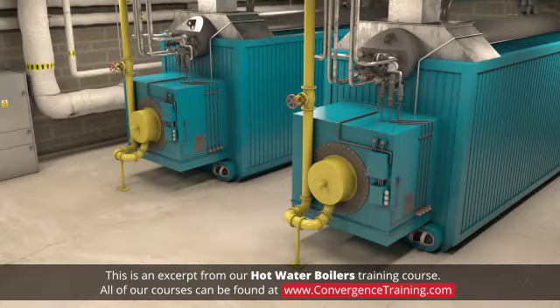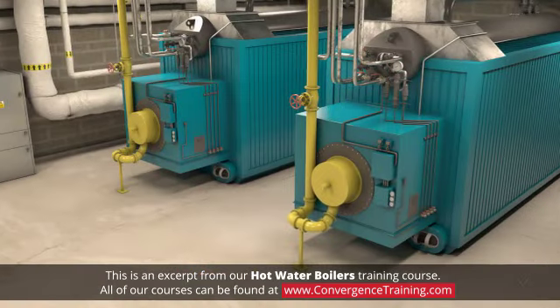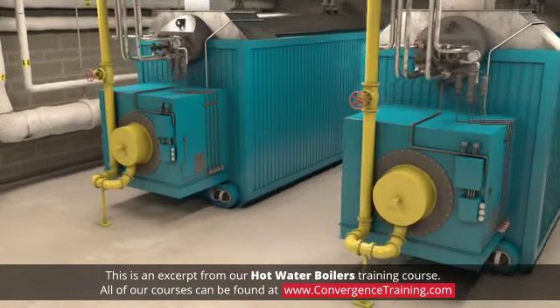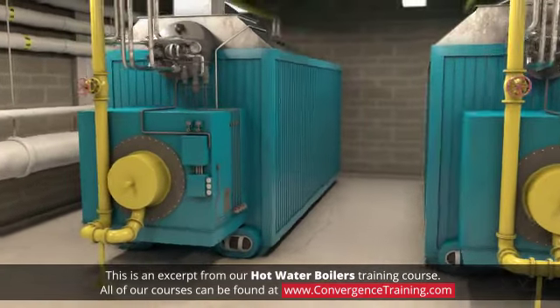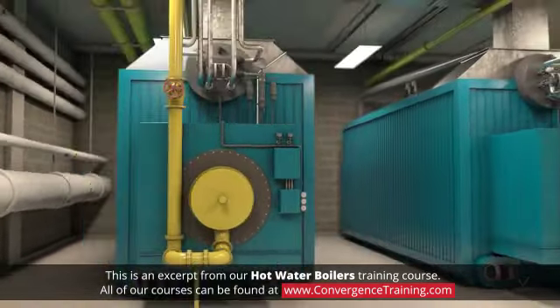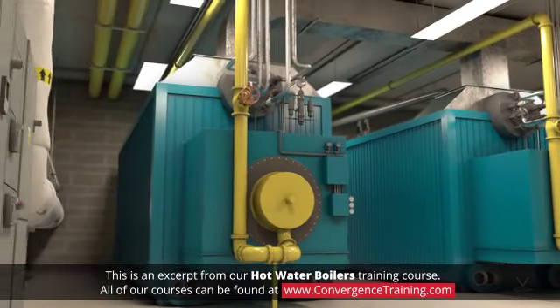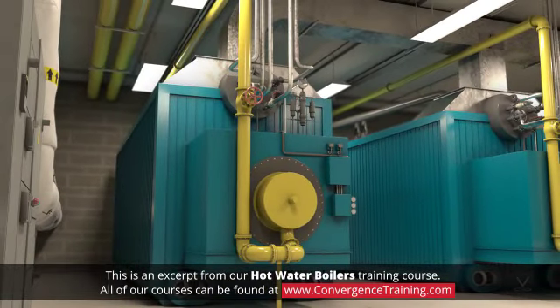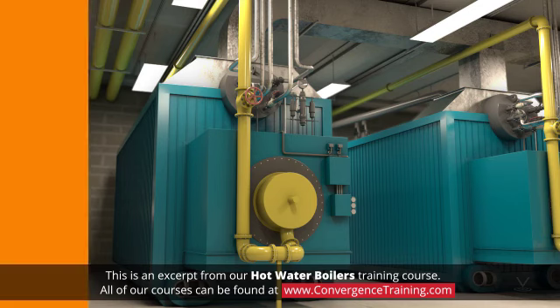the tubes. Also, because water tube boilers contain less water than fire tube boilers with the same capacity, they are inherently safer, have faster response times, and are available in larger capacities. Also, unlike fire tube boilers, tubes can be added to some installed water tube boilers to increase their capacity.